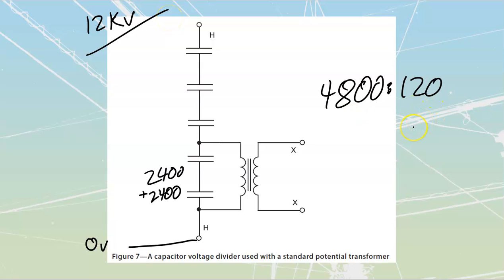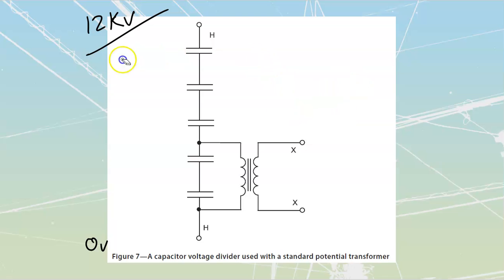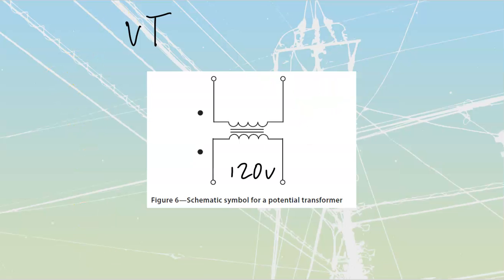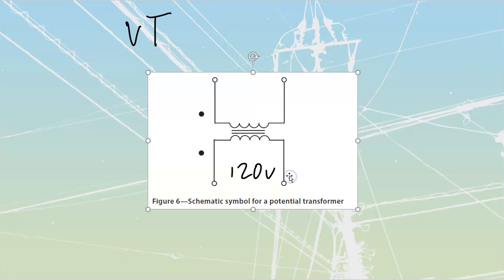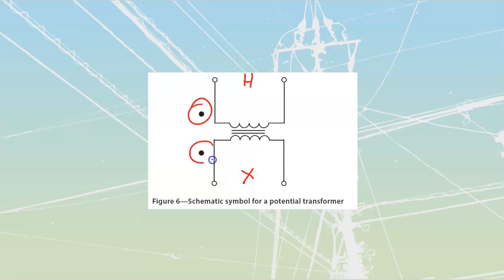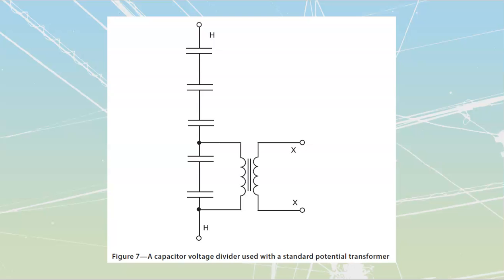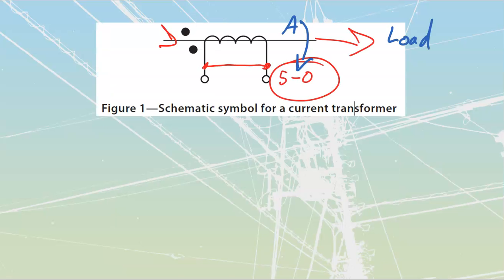Last thing to talk about with our PTs is that they are all polarity sensitive and polarity regulated, meaning they'll have dots on them. We don't necessarily have the H's and X's—if they do have an H, it often just says H on one side, X on the other, but they won't use the 1s and 2s, they'll use these dots. What we need to do is connect the dots later on when we do our connections, making sure they're all aligned together. We'll do that in our next learning task where we'll look at the connections and readings we get off of them.